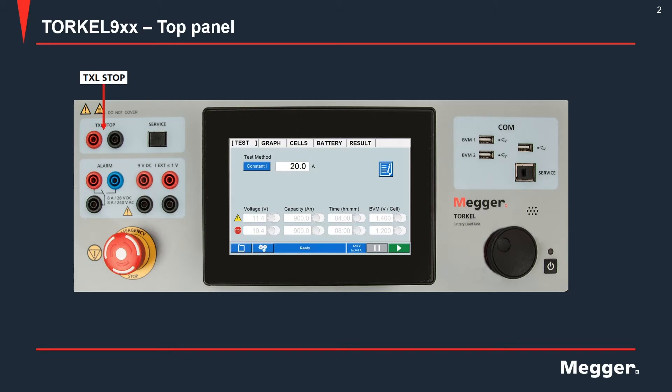On the top left you have the TXL stop terminals or binding posts. Whenever you are using an external load unit in parallel with the TORKEL for drawing more current out of the battery bank, you would run a pair of cables from these terminals to the extra load unit. Whenever the discharge test ends — because of you manually stopping it or the limits being exceeded — a control signal will be sent out from these terminals to the extra load unit and the breaker on the extra load unit will trip.